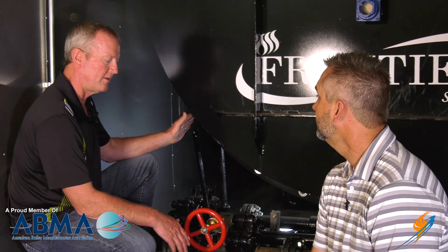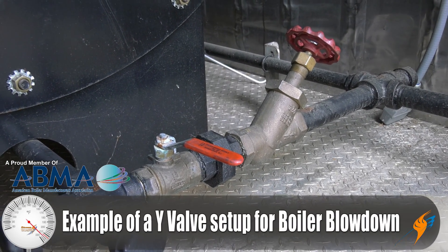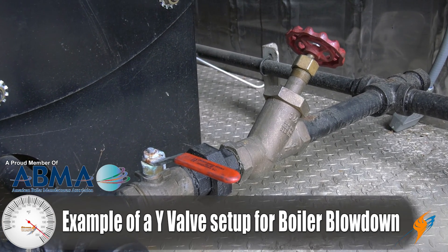This particular design is common, but there are other designs — for example, a ball valve and a Y globe valve. The knife blade valve is very common, but you can also use a standard full-port ball valve as your quick valve, paired with a Y-pattern globe valve where the handle and stem sit at an angle. That combination is used quite commonly as well, but it's a low-pressure type — you can't exceed about 250 PSI with that style of valve.